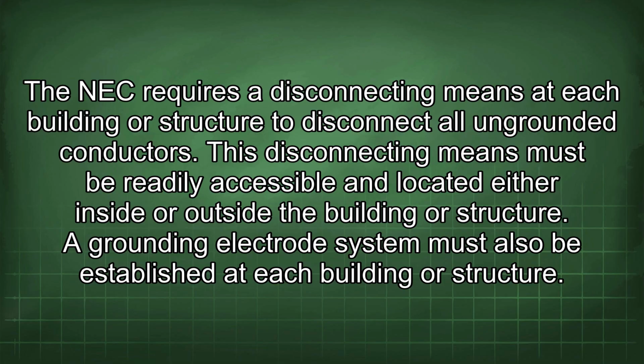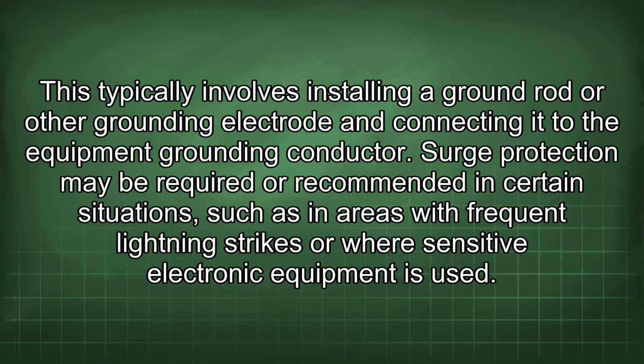The NEC requires a disconnecting means at each building or structure to disconnect all ungrounded conductors. This disconnecting means must be readily accessible and located either inside or outside the building or structure. The grounding electrode system must also be established at each building or structure. This typically involves installing a ground rod or other grounding electrode and connecting it to the equipment grounding conductor.